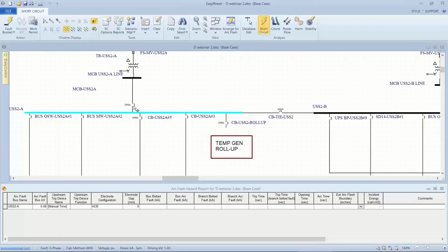But at the same time, what's going on up here is, and the original report was maintenance mode isn't working. If I turn maintenance mode on, in fact, it works quite nicely as long as I don't have this breaker engaged. So the result is maintenance mode works great. The scenario needs to consider whether or not this is a realistic load in normal operations. And I need to reflect on how I'm going to control my setup, including the 2-second rule.